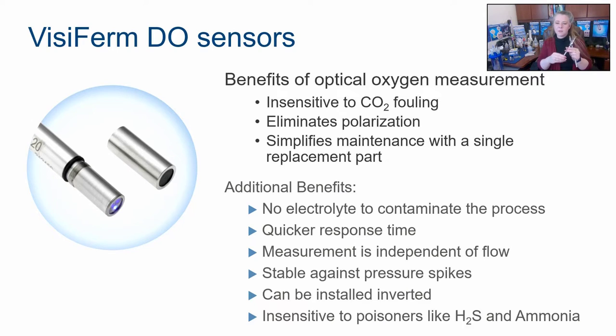The whole maintenance on this is replace this cap when it goes bad. Oh, and there's a tiny O-ring inside, but that's just for sealing. So optical probes are also faster in response time than polarographic. And because there's no electrolyte, I can actually install it upside down if I wanted to.